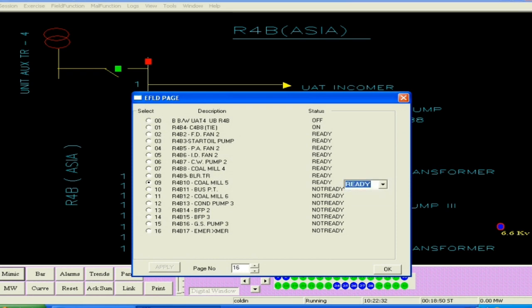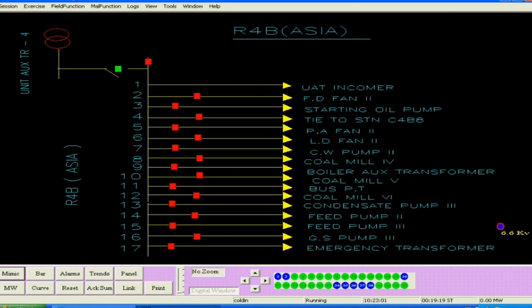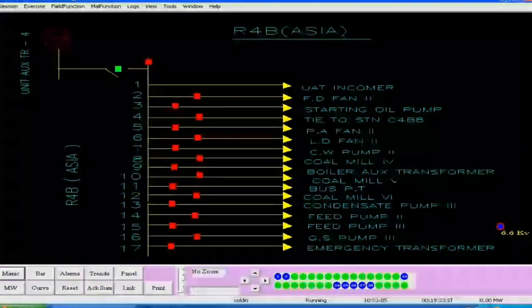So these breakers are to be made ready, and after this, R4A and R4B, that is the unit boards, are charged, then we can move on to the boiler board and the low tension auxiliaries. So you will see that all the breakers are being made ready, and after you make all the breakers ready, you can check it in the mimic also. So the breakers have been made ready. This is the R4B board from where we have made all the breakers ready.